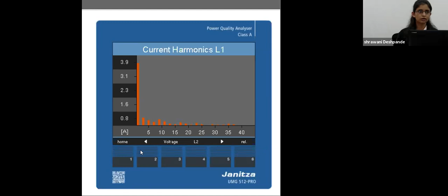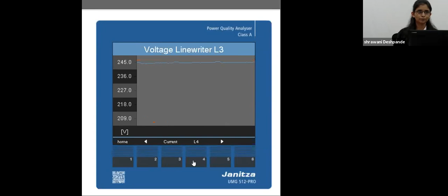Then the next is the line writer screen. On this, we can see the actual waveform or actual representation of various parameters. Right now you are seeing the R phase voltage. Similarly, we can have it for all the phases. Then we can have it for current, active power, reactive power, residual currents, and for internal and external temperature. As I said, this meter has a feature where we can connect an external thermistor input to it, so it can show external temperature as well as internal temperature.